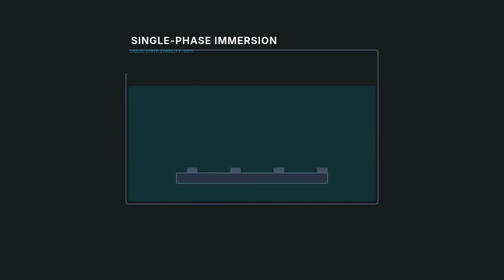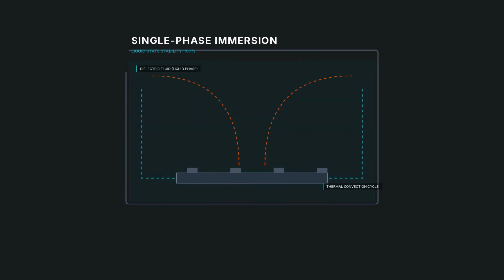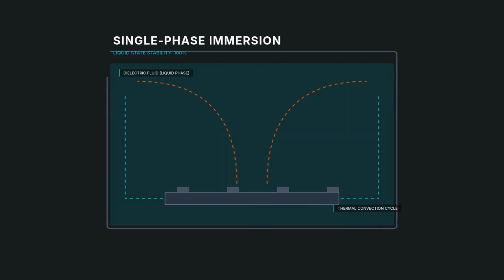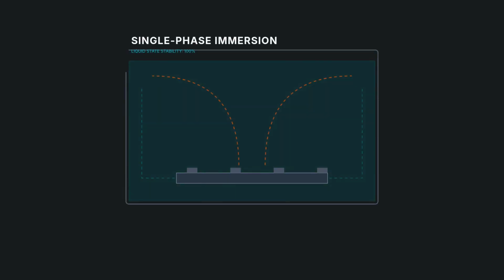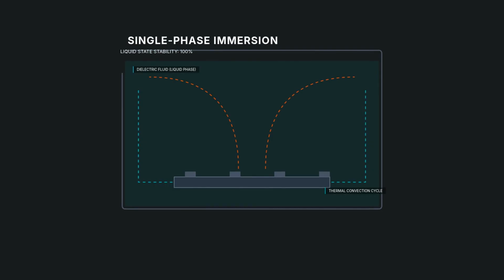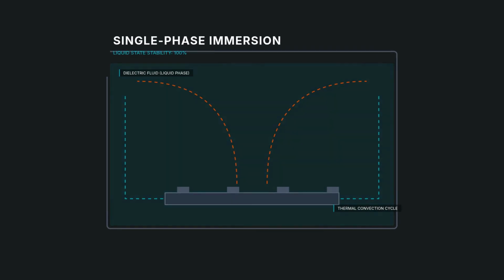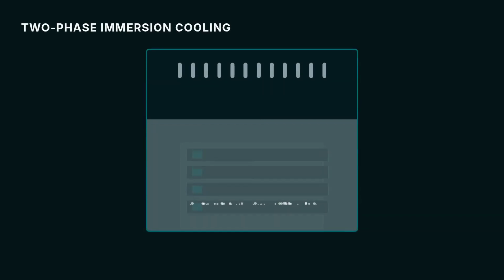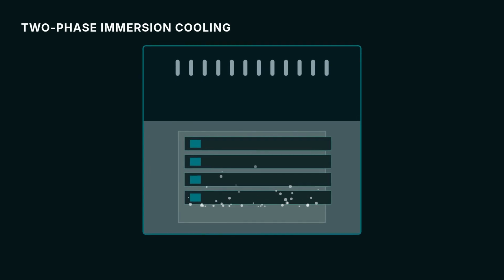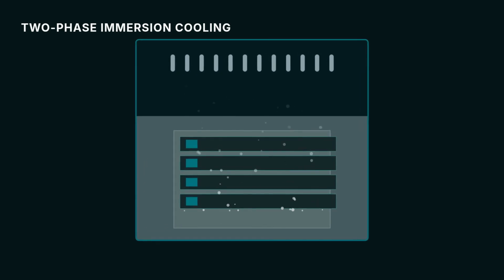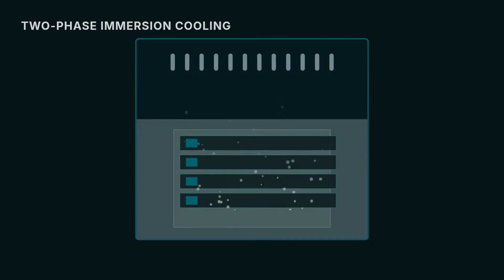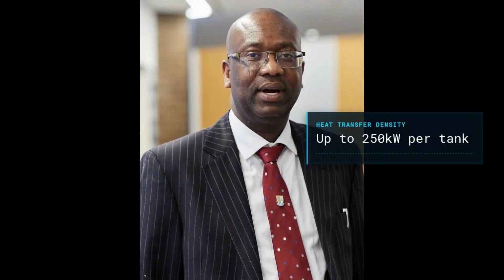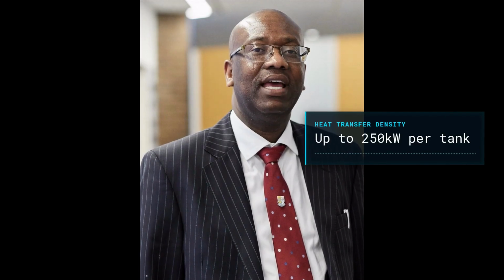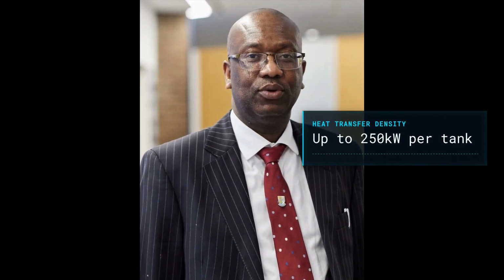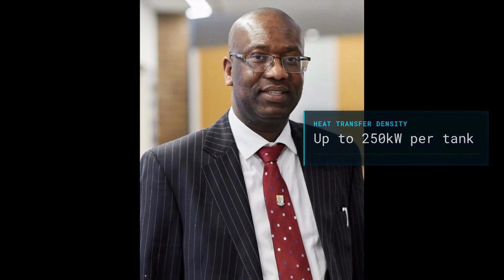Single-phase immersion is the more mature technology. The fluid remains in a liquid state throughout the cycle. In two-phase immersion, the fluid boils at the component surface, creating vapor that condenses and returns. This latent heat of vaporization allows for extremely high heat transfer density, suitable for the densest AI chips.